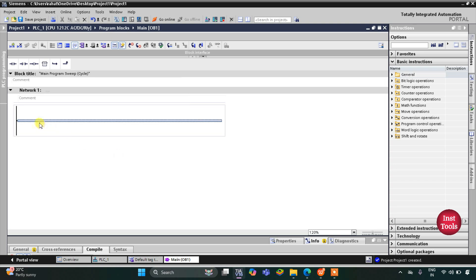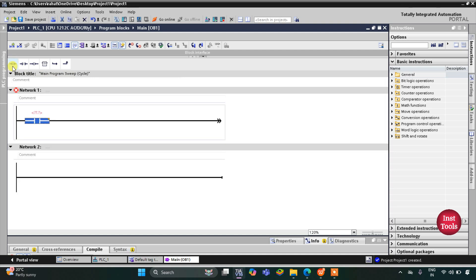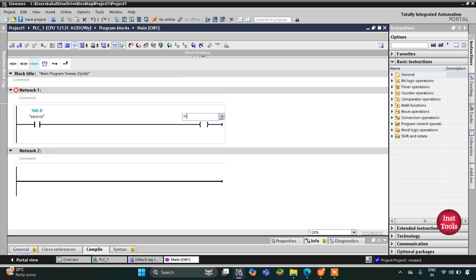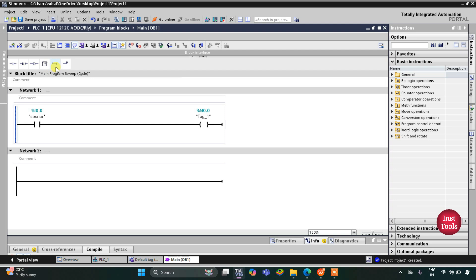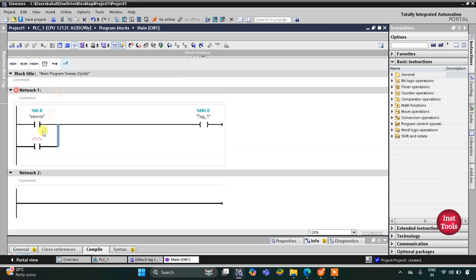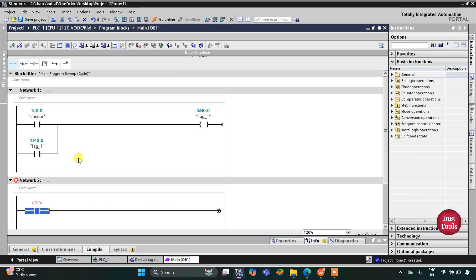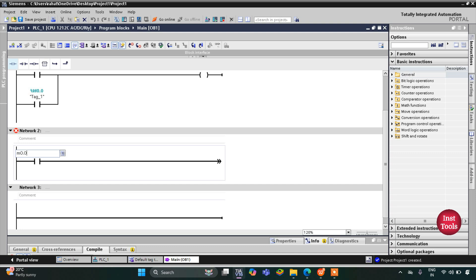Here we will draw the ladder logic. First I will insert a normally open contact for the sensor and then a coil. The normally open contact is for the sensor and the coil is for memory bit M0.0. Then I will latch it by opening a branch, adding a normally open contact assigned to M0.0, and closing the branch.